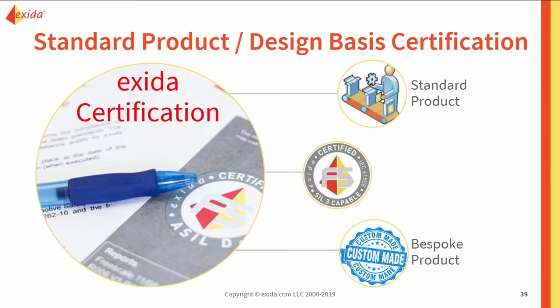Now, this can be done on a standard product or a design basis product. So this could be for a standard off-the-shelf product of this valve always with this actuator, always with this solenoid in this nice package. Here's your certificate with these failure rates always associated with them. However, that's not how the world always works, and we understand that. So we are using the same process and procedures that we use in certifying a bespoke device or a custom device. We follow the same process and procedures from the standards, but for the integrated process.